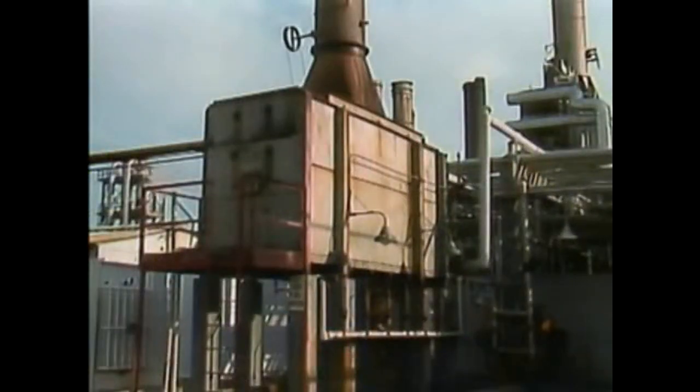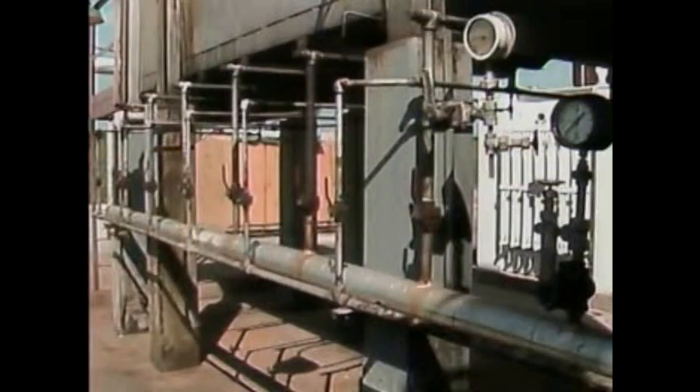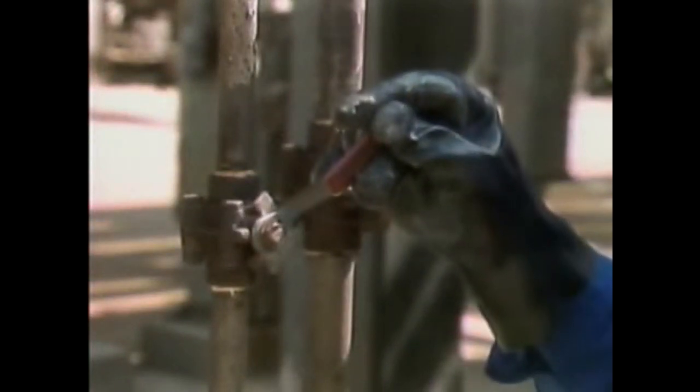In this part, we'll look at furnace fuel system problems. Fuel problems can arise when the flow of process fluid is significantly reduced and it's necessary to operate the furnace at a lower firing rate. At a reduced firing rate, it may be hard to supply enough fuel to the header to keep all the burners going. To avoid this, the operators may close off some of the burners and their registers so that no fuel is sent to them.